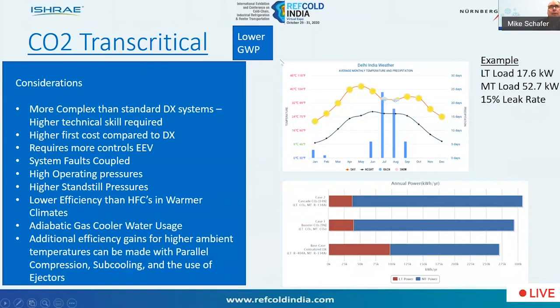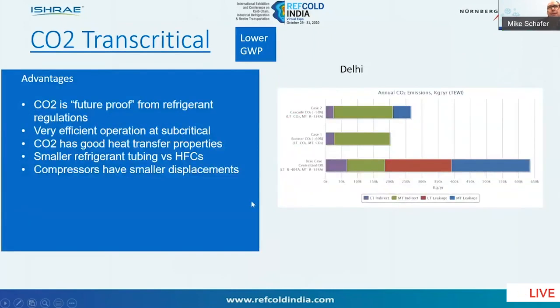So looking at the advantages of transcritical using natural refrigerant CO2, obviously this would be that it's future-proof in terms of refrigerant regulations. The system operates very efficiently at subcritical, and as I mentioned, there's a number of strategies to improve upon the standard booster system, such as ejectors and parallel compression.